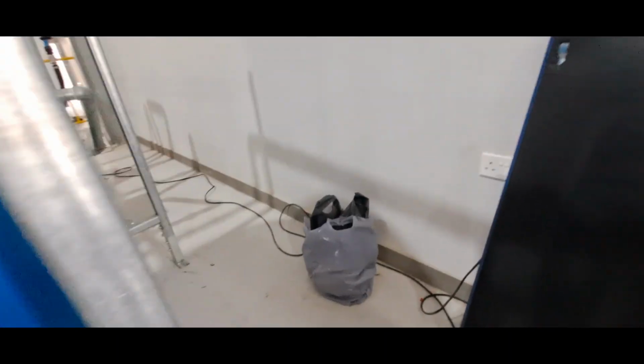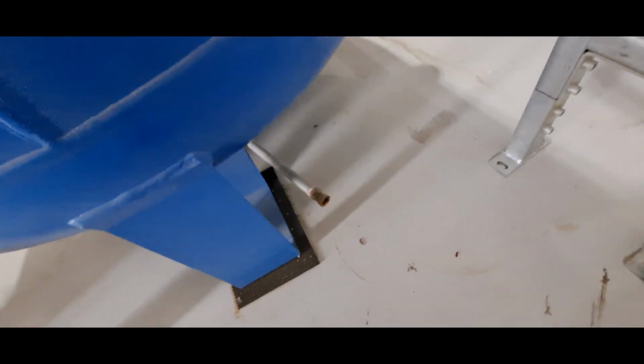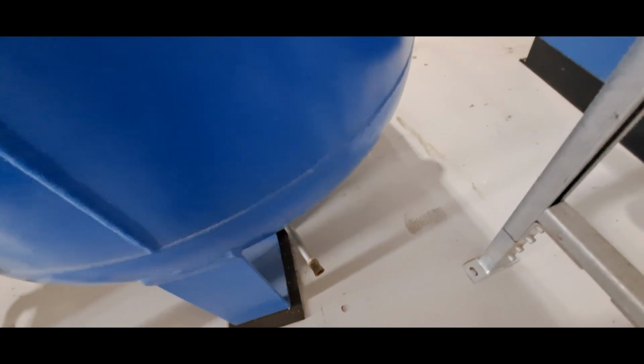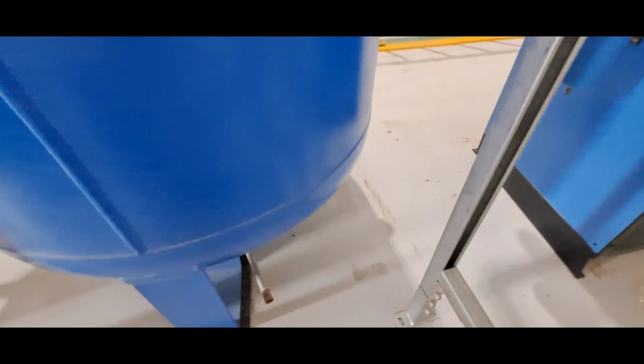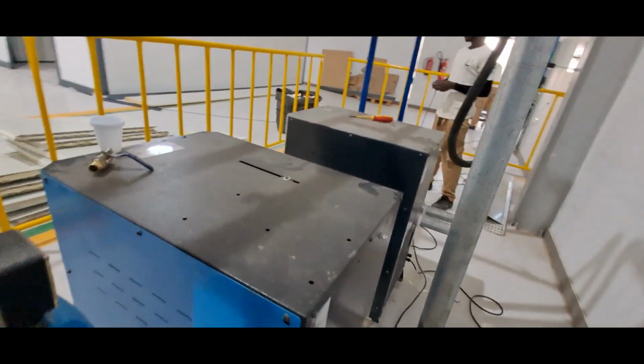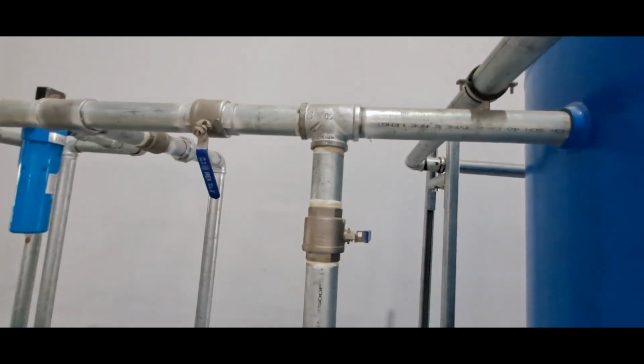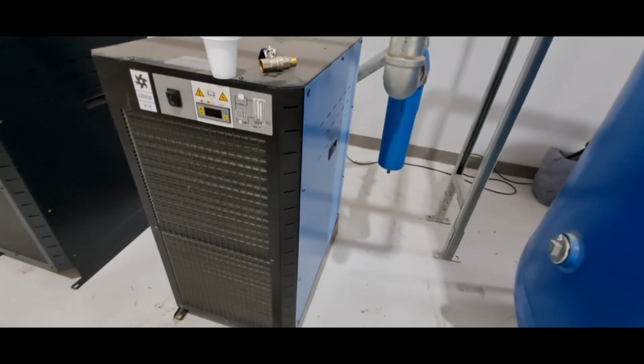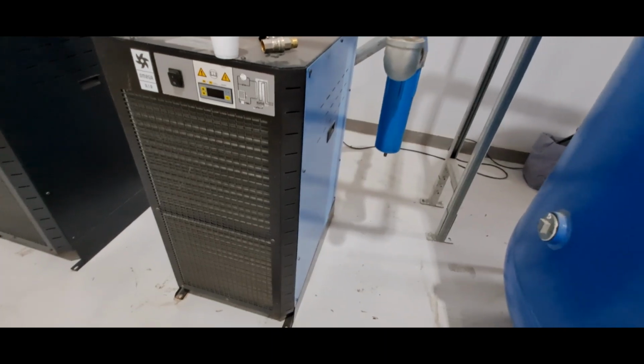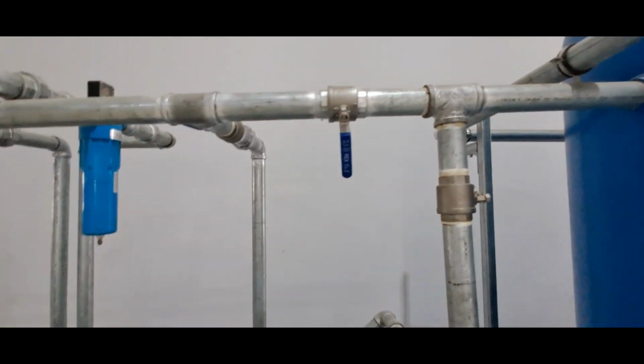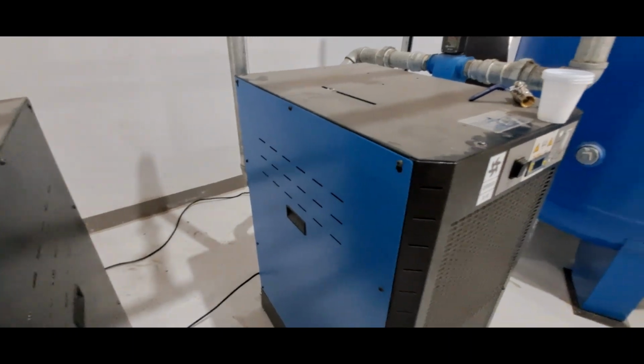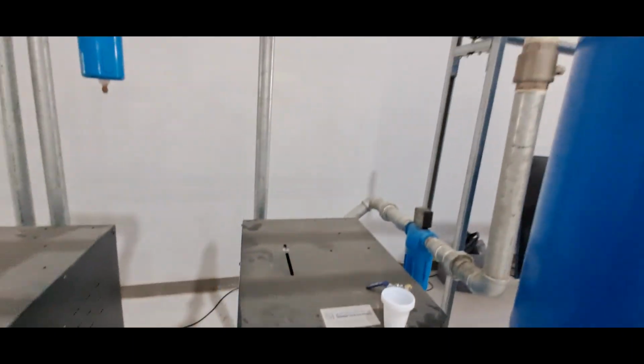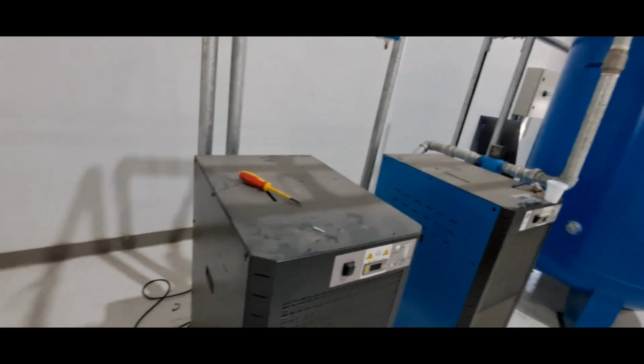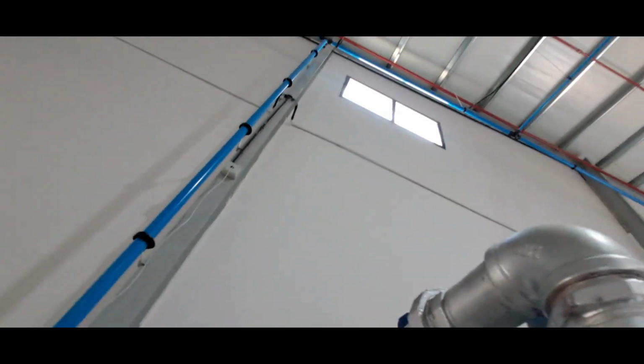And you have the drain. So basically there is an auto drain here. If there is moisture or water accumulation inside, the auto drain will discharge the water. Then after the tank, it will go to the air dryer to cool down the compressed air and to remove the condensate water. The same, it also has a moisture discharge system. Then moving forward, after the air dryer, it will go to the main header line towards the machineries.